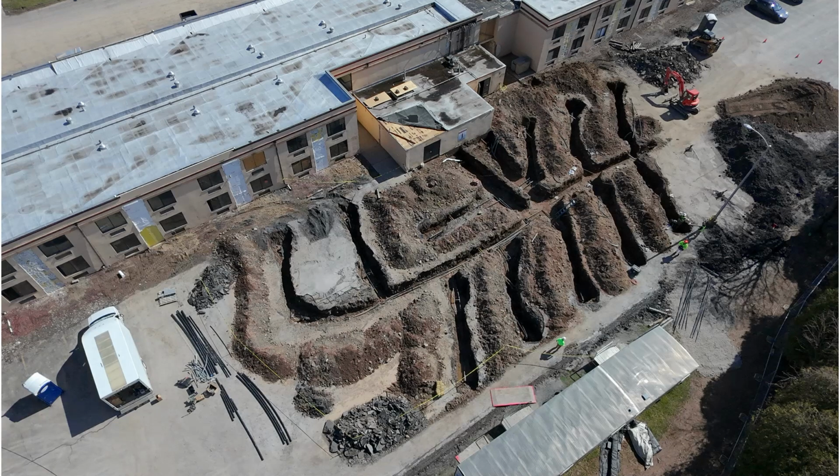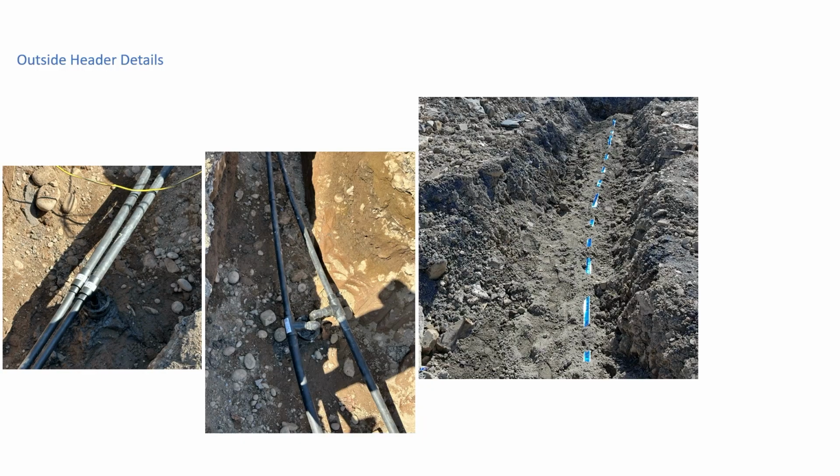And you have to run the pressure drop. But again, the pressure drop difference here, whether they are 20 feet more or less on one circuit or not, is irrelevant because you're already pumping at 1,000 feet through the ground. So this is how it looks in reality. You see here, sometimes we do elbows here. Depends a little bit on how the driller ended up and the cutting ended up. Sometimes we just put it on top of it, and we come with a 2-inch line here, branch off in 1.5 inches, continue with 1.5 inches to the next borehole. That's it. Simple. And let me ask you this. Are we designing return headers inside the building ever?